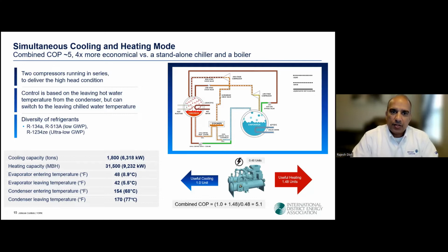The refrigerant gas leaves the evaporator section and passes through the low-stage compressor onto the high-stage compressor and finally into the condenser. The condenser is also of shell and tube design, wherein the hot water is flowing inside the condenser tubes. This is our sink. The gas baffles distribute the refrigerant gas over the entire set of condenser tubes, due to which the unit produces hot water, which is also used for beneficial heating. The heating capacity that we get out of the condenser is equal to the heat removed in the evaporator plus the compressor work that was done. The economizer that you see in this animation helps to improve the overall cycle efficiency. In the simultaneous cooling and heating mode, the control is based on the leaving hot water temperature, but can switch to the leaving chilled water temperature if need be.